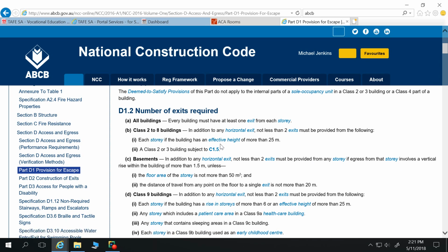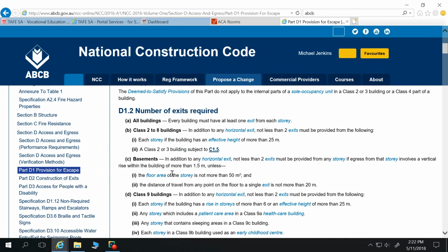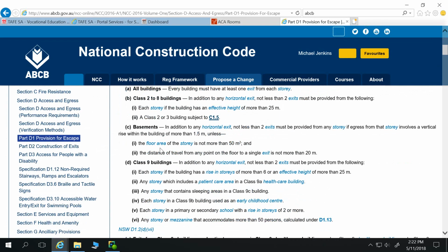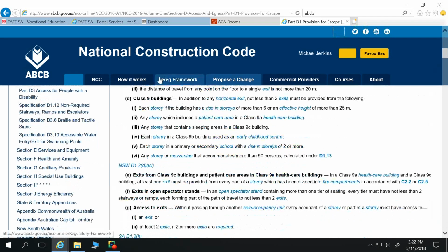So each story in the building must be provided with an exit. In addition to any horizontal exit, not less than 2 exits must be provided from the following. Each story, if the building has an effective height of more than 25 metres, so we're not that. So at the moment we can still get away with 1, possibly. A class 2 or 3 building subject to C1.5. Well, we're not a class 2 or 3 building. But subject to C1.5, we can quickly have a look at what that is. That's the concession for being a lower type of fire construction. We're not a class 2 or 3 building, so we don't need to worry about that. We're not designing for basements in class, and we're not a class 9 building.